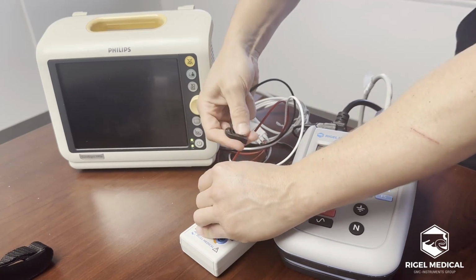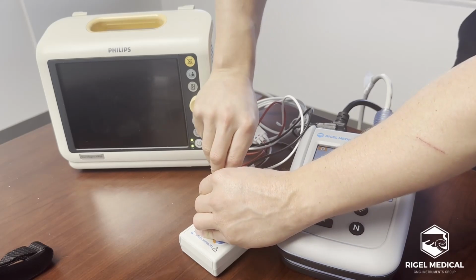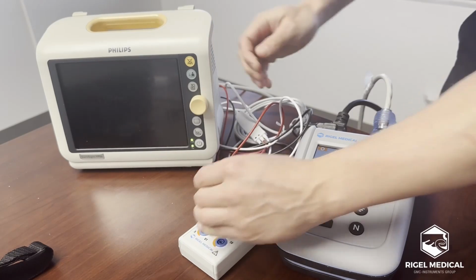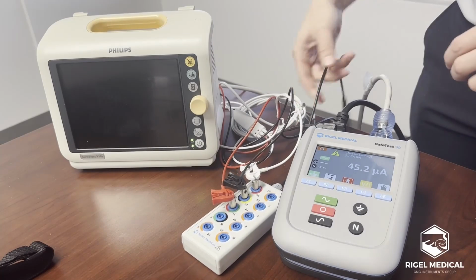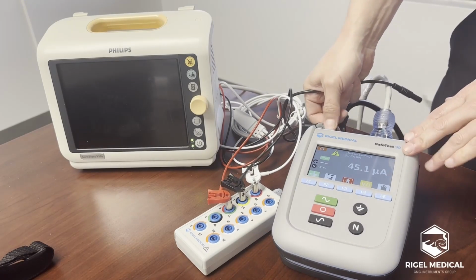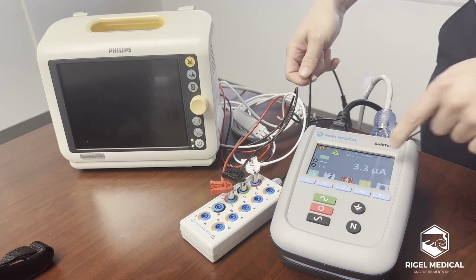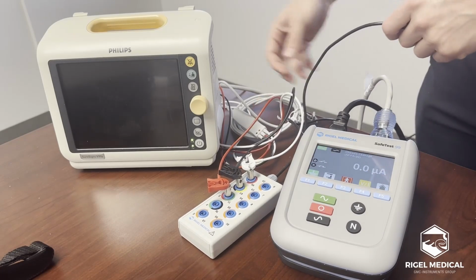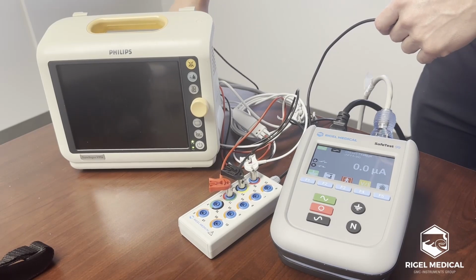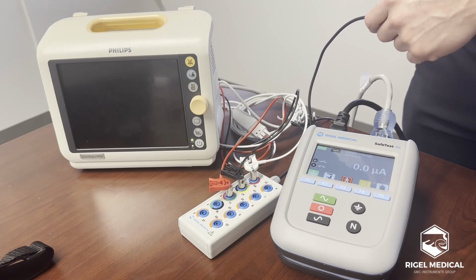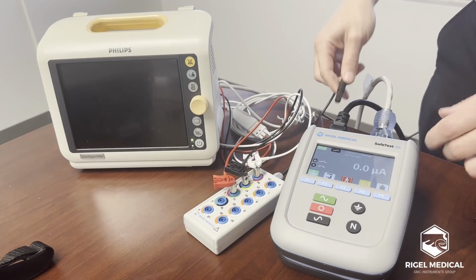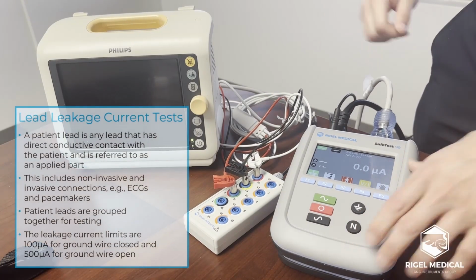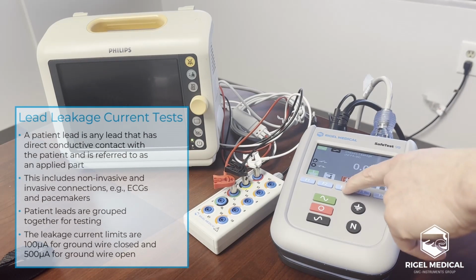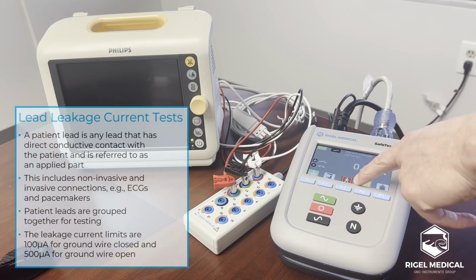There's no ECG simulation. So I select that, and then I disconnect my probe from the analyzer. Hit the red button, that stops the test. I can now take the probe from the rear of the analyzer, that's no longer needed. And then I connect the ECG box to the 4mm socket where the probe just was. Patient leakage is simulated here, so that's F3.